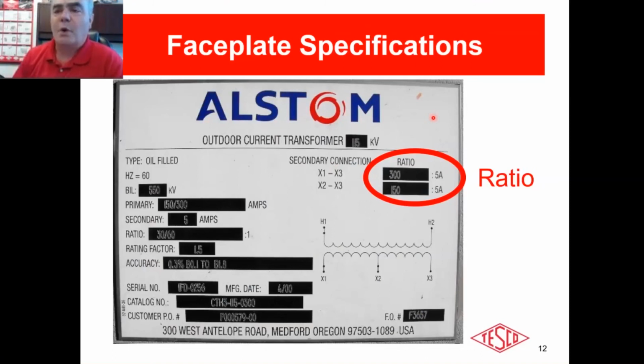All right. So this is just one of several current transformer companies. In this particular case, I've picked one that is what we call a dual ratio. These were very popular back in the 1990s. They came into vogue, and they allowed the utilities at the time to reduce the number of SKUs that they had, because depending on whether you connected X1 and X3 or X2 and X3, you could create a ratio of 300 to 5 or 150 to 5. Now we are moving to extended range transformers, which accomplishes the same purpose in that you have fewer SKUs in stock to cover a much wider range of applications.